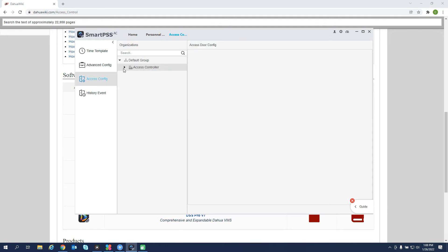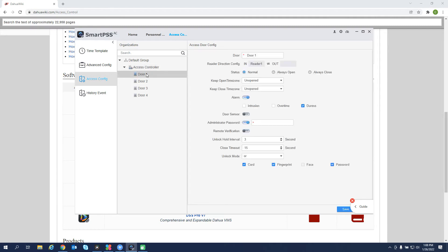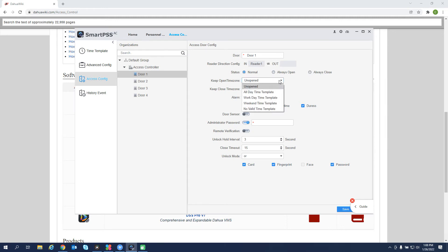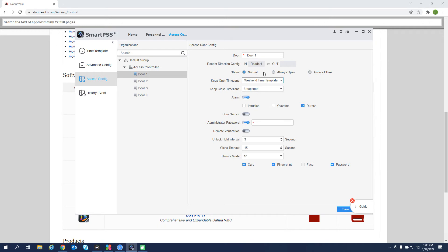And then under access config, we can go in per door, rename the door. If we want a keep open time zone, let's say we did create that time template that we want a door to open between let's say 7am and 5pm. You would create that time template and then assign that here. Door sensor. If we had a door contact on the door and we want to be able to see if that door is physically held open through the software here, we would enable the door sensor.